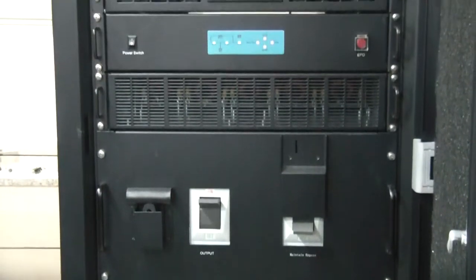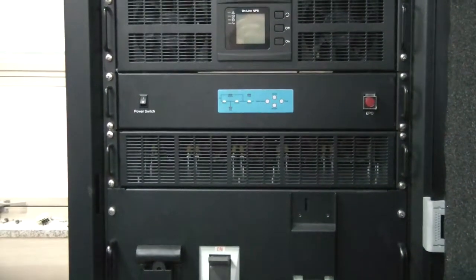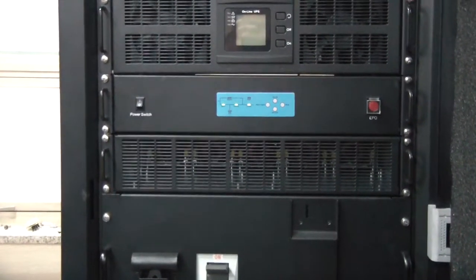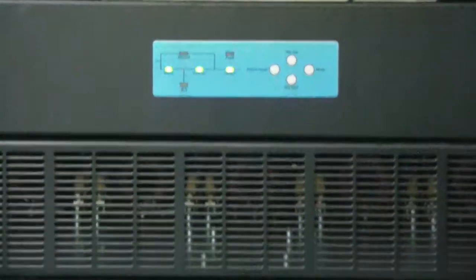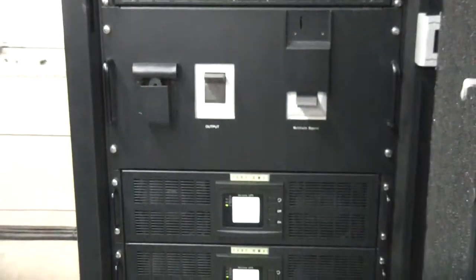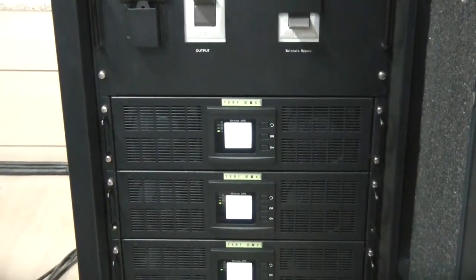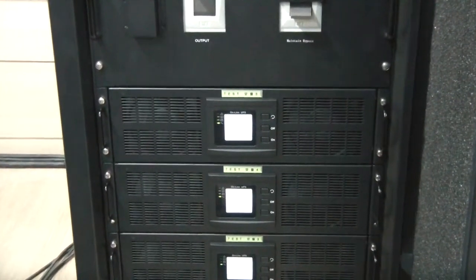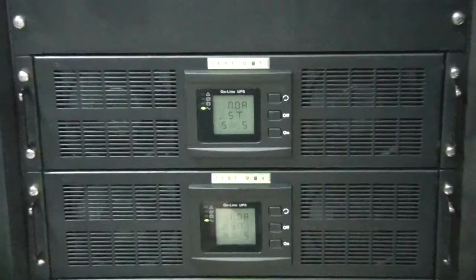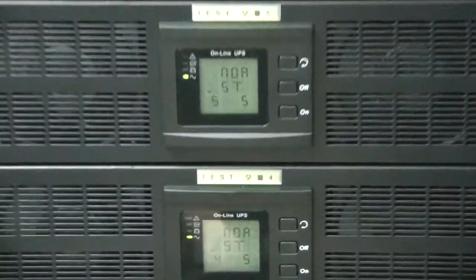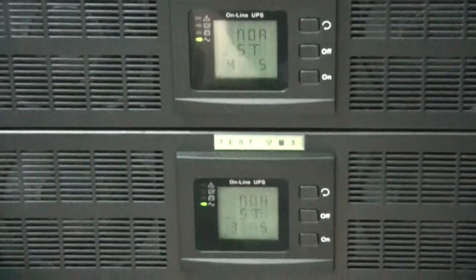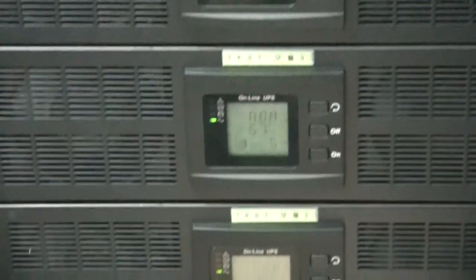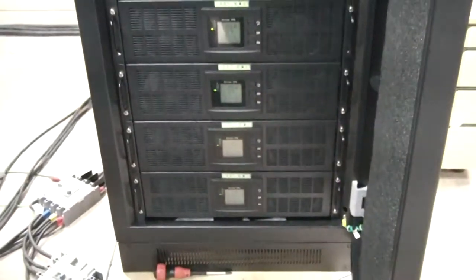The advantages of our modular UPS are as follows. Number one, high efficiency, 95% over. Number two, complete repairing in the way of only replacing the module. In case of a stand-alone UPS, we should stop operating.